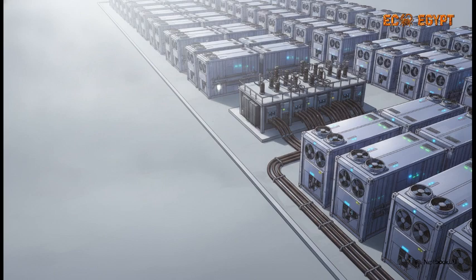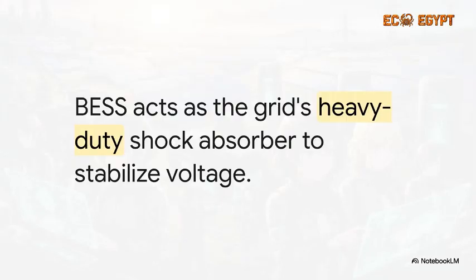And what's truly amazing is its output capability. It can deploy 20 megawatts of active power support for 30 minutes straight, all while safely operating at a 92% depth of discharge. You can really think of this system as the grid's heavy-duty shock absorber. Whenever that massive PV plant we just talked about experiences a sudden drop in generation, say a giant cloud rolls over, or if the local grid suddenly gets weak and the voltage drops, this battery system instantly kicks in. It pumps out reactive and active power to balance the load and prevent a cascading grid failure. It is literally the ultimate stabilizer.